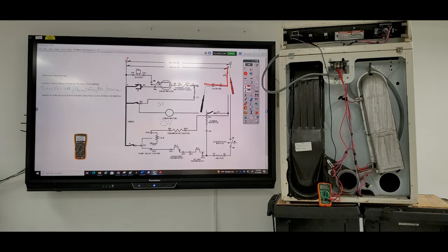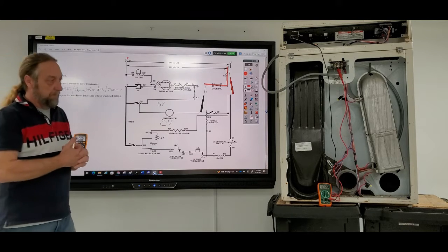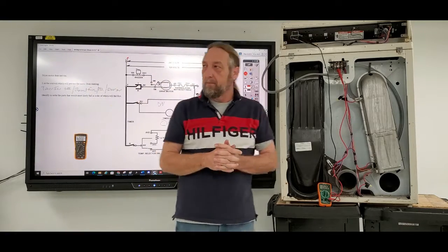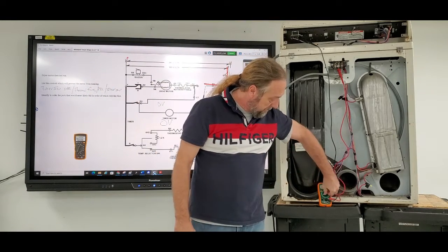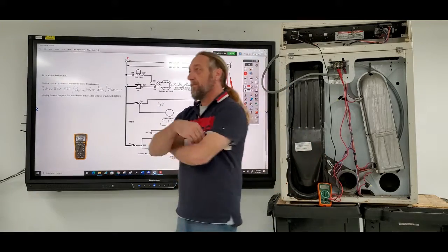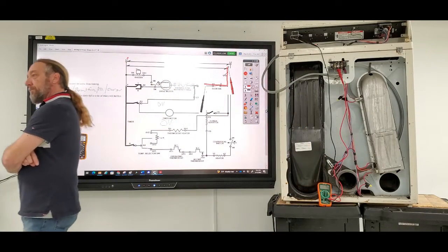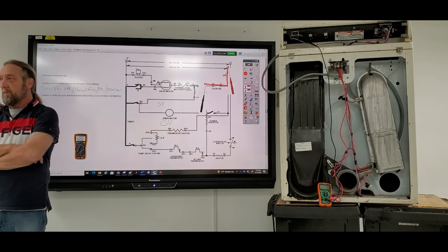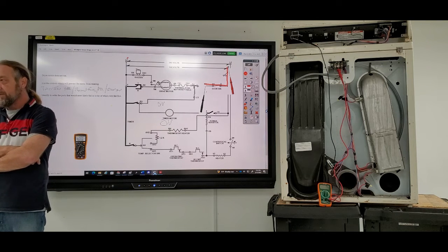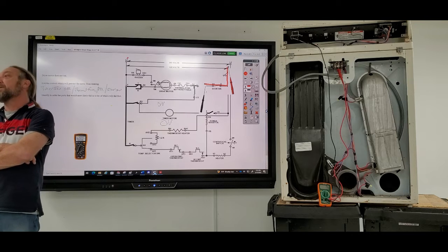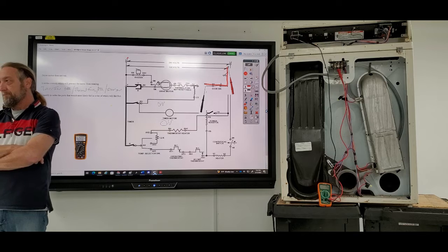Yes, sir. So you said something about a scientist -- when they do an experiment, even if it's not successful, it tells you something, right? Mm-hmm. So in the initial scenario, you were talking about saving time, and then later on you said that when you're testing for voltage, you're testing the circuit, not the load, correct? That is correct. So in a situation where you went directly to the motor, you take everything apart and test the motor while it's running. Okay, that's not telling me definitely the motor's good or bad.